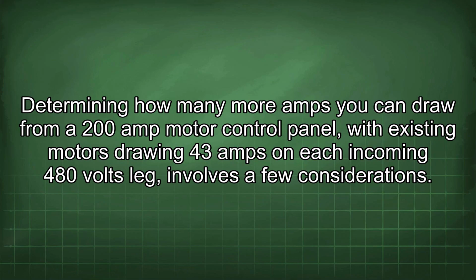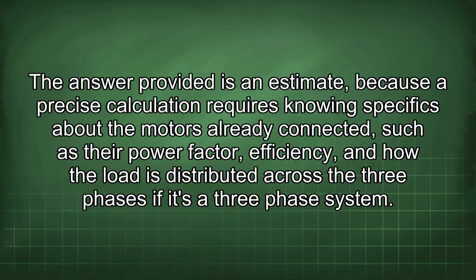Determining how many more amps you can draw from a 200 amp motor control panel, with existing motors drawing 43 amps on each incoming 480 volt leg, involves a few considerations. The answer provided is an estimate because a precise calculation requires knowing specifics about the motors already connected, such as their power factor, efficiency, and how the load is distributed across the three phases if it's a three-phase system.